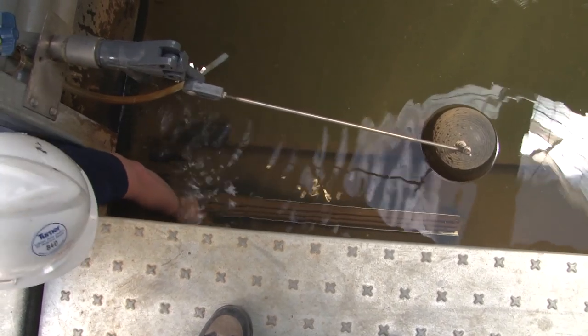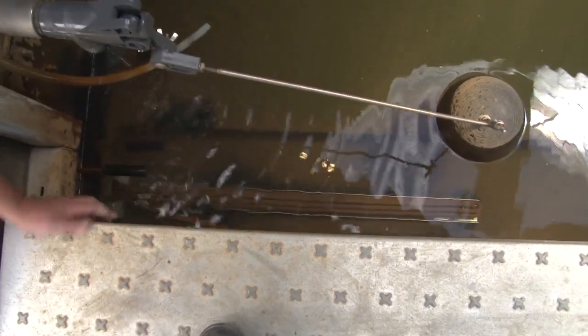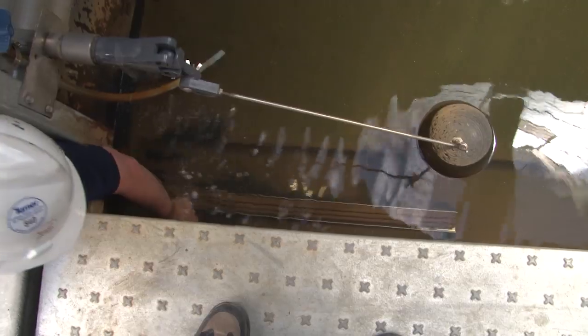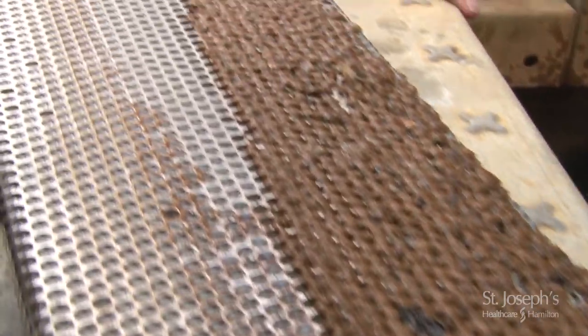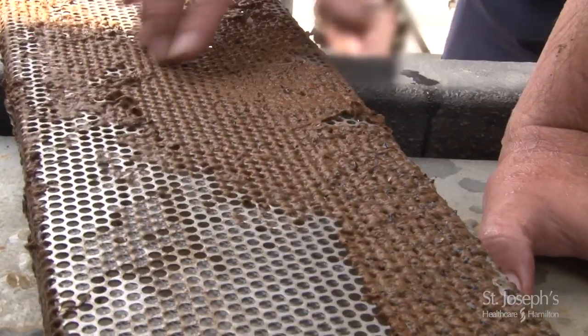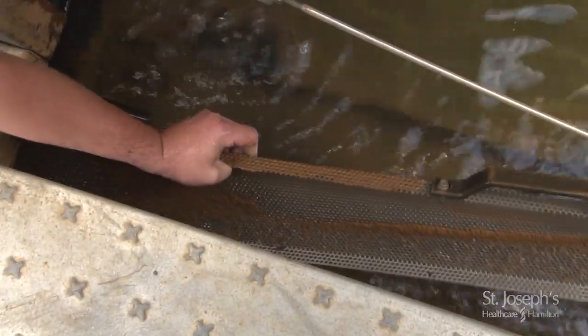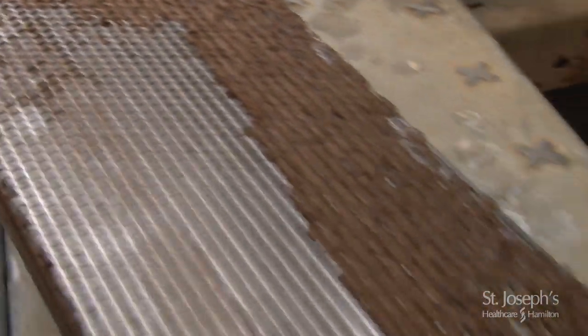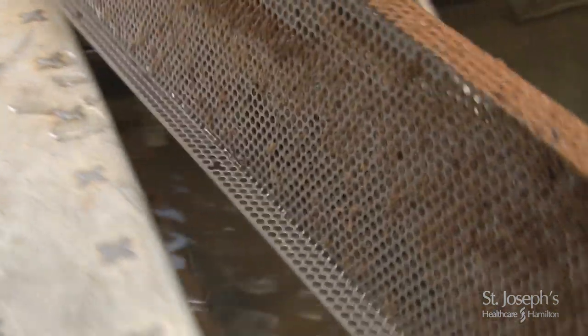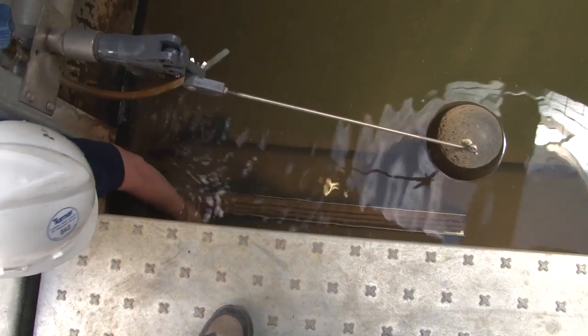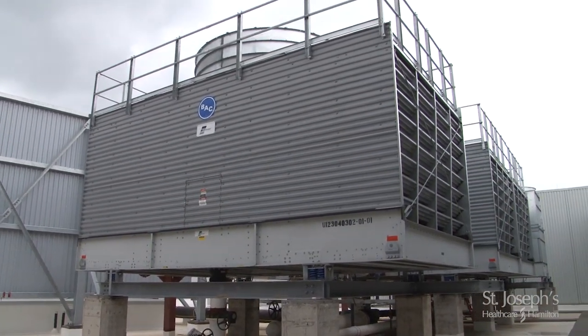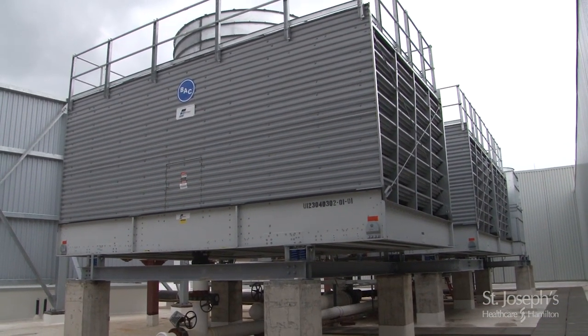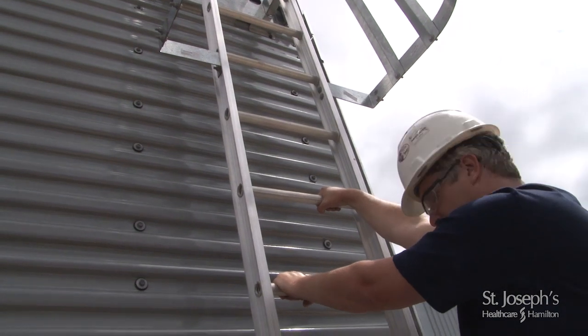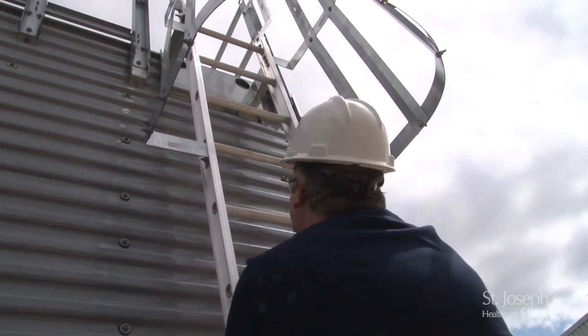That is the heater that enters the cold water basin, and that's what keeps the basin from freezing in winter operation. Right next to it, there's a filter assembly. There is some buildup on it now. But what we need to do on a monthly basis is pull these filters out and just wash them off with a garden hose, which is usually all that you need to do, and then they just reinstall back into the side of the tower. The last place we want to go is up to the top of the tower, where we're going to have a look at the hot water boxes where the water enters the tower.